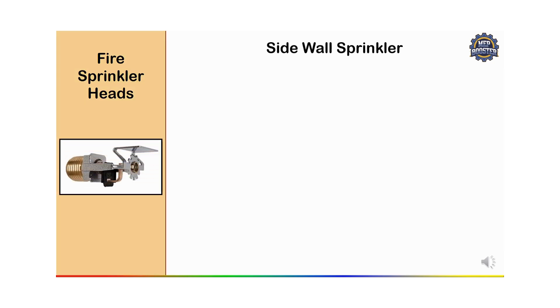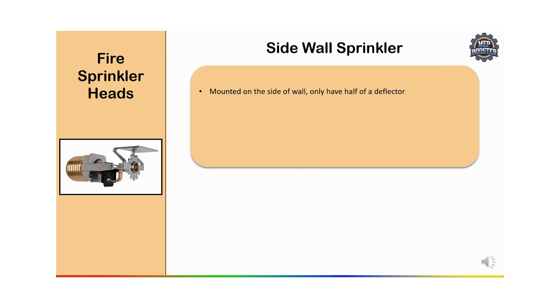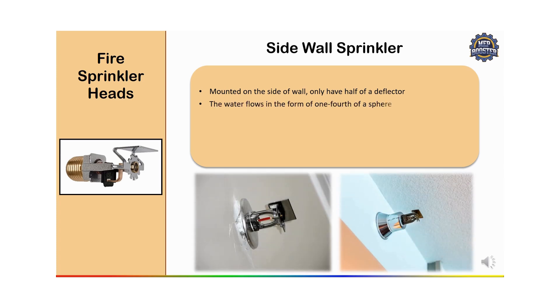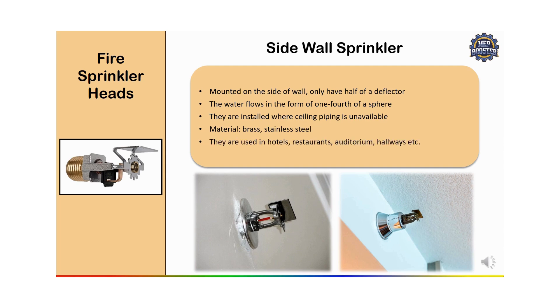Then we have the sidewall sprinkler, which is mounted on the side wall and has only half of a deflector. It is mounted on the wall and distributes water horizontally, making it ideal for areas with limited ceiling space or irregular shapes. It is installed on the sidewall with the deflector facing outward. Water flows in the form of one-fourth of a sphere. They are installed where ceiling piping is unavailable and are used in hotels, restaurants, auditoriums, and hallways. Sidewall sprinklers are suitable for narrow or irregularly shaped rooms.